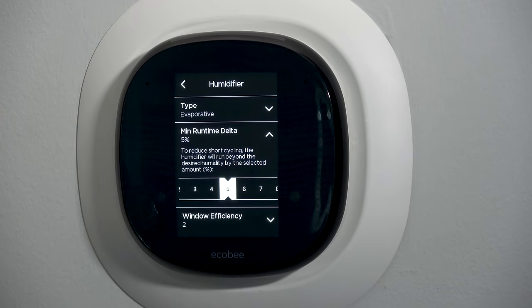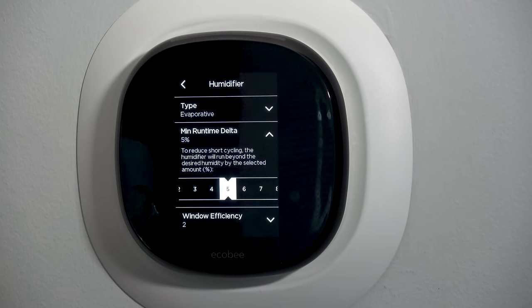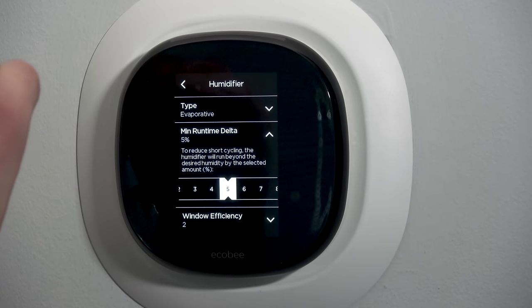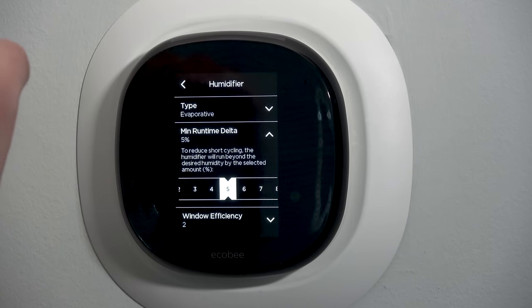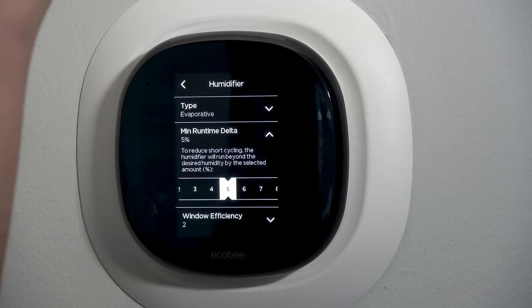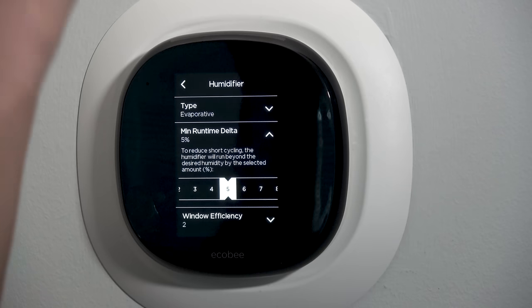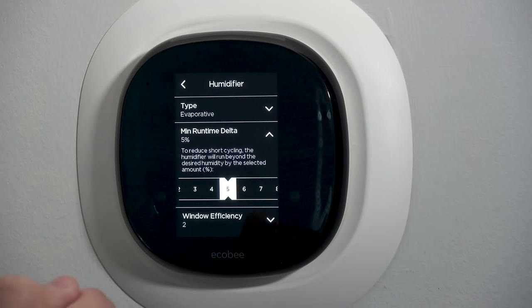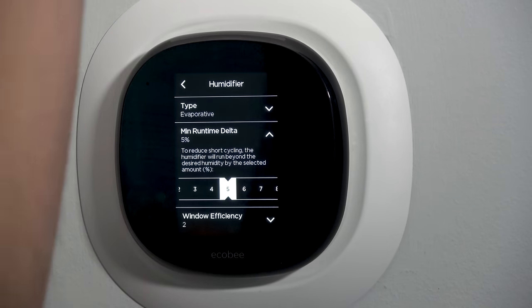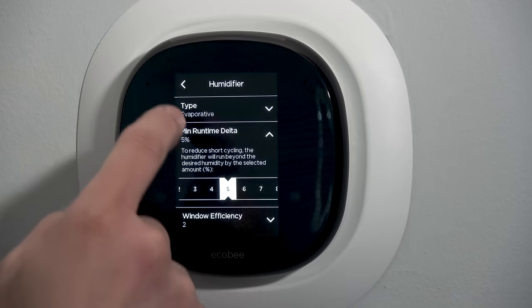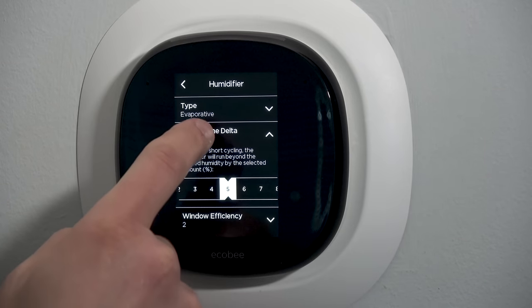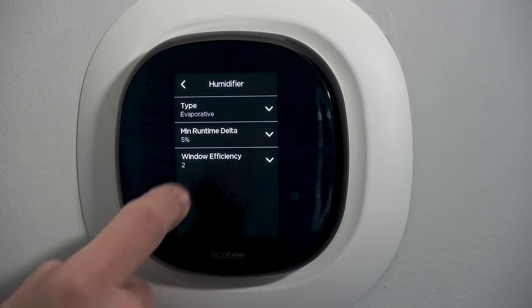Minimum runtime delta — five percent is pretty good. That means it'll turn on at a certain humidity and then drive that humidity up five percent and turn off. When it drops back down five percent it'll turn on and drive it back up. That's a pretty good place; you can change it if you need to.